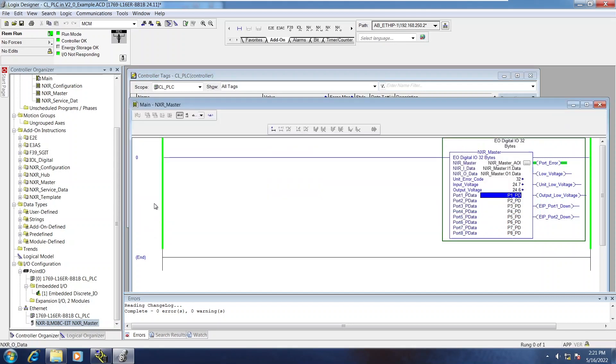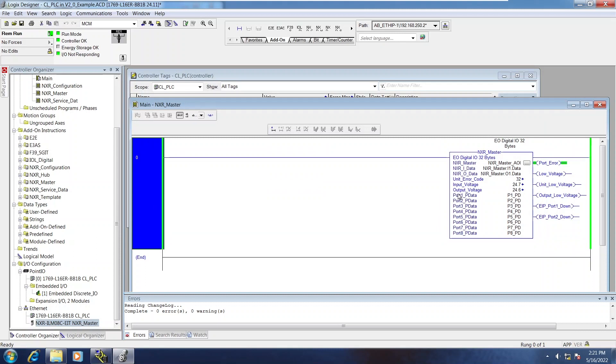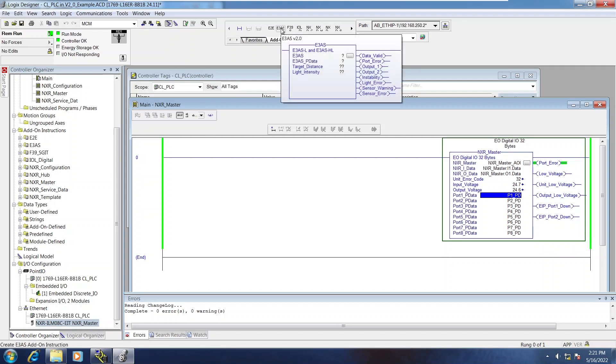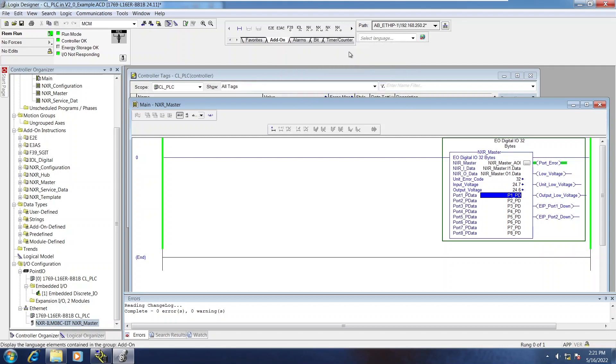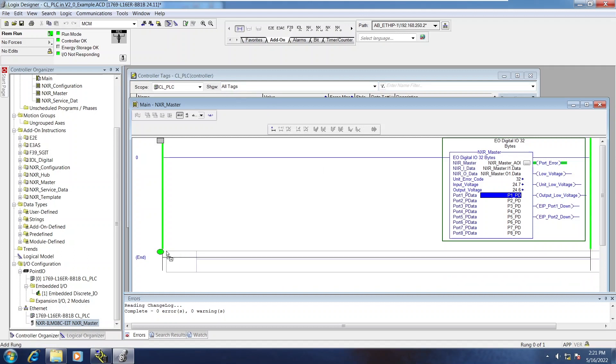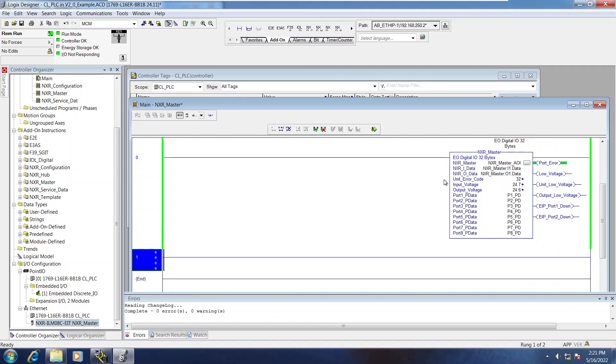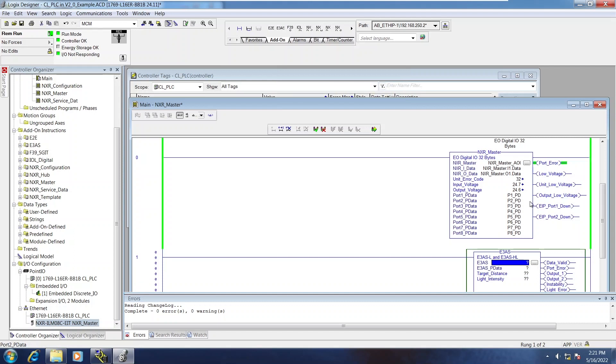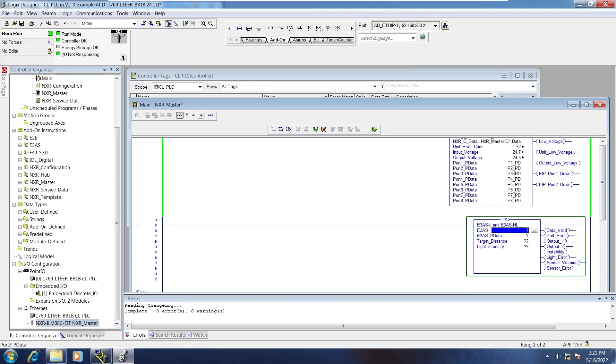Now the device level AOIs are going to take this pData variable and depending on the type of device AOI that's used, they're going to extract the relevant information from them. So I'm just going to do one of them. I don't need to go through all of them here. I'll use the E3AS since I have one of those on port one right now.